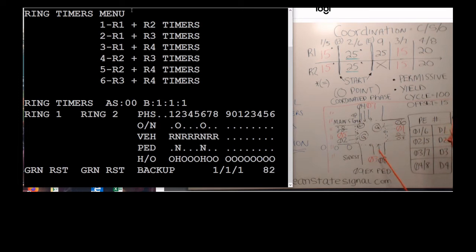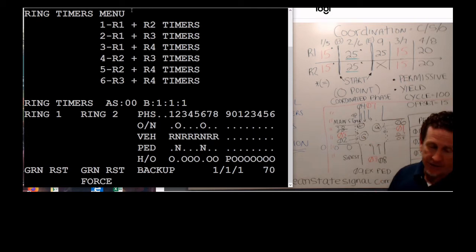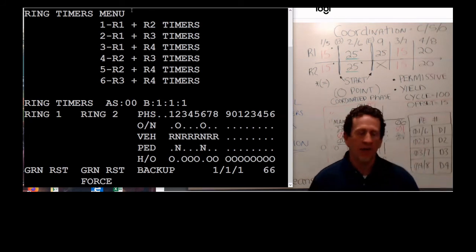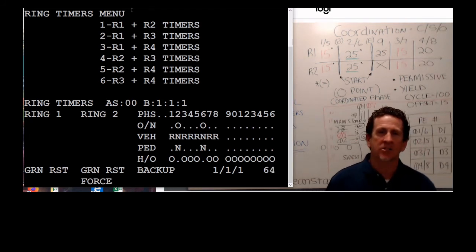It can bring 3 up, and we can do 3 and 8 because 4 is not on. If the controller already makes the decision to go to 1 and 5 next, and somebody pulls up on 3, it's too late. 3 has to wait until it comes around again. So that's the term we say, the next decision. The controller's already made a next decision to go somewhere else in the sequence.